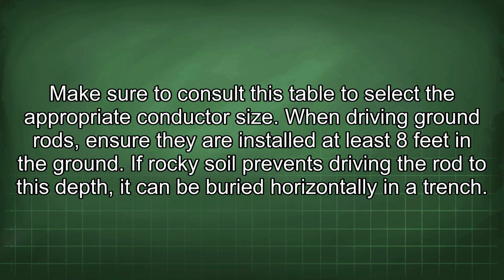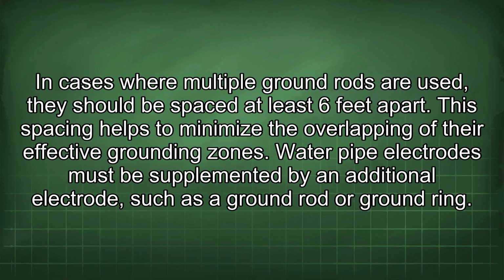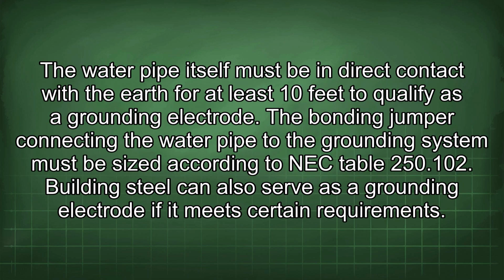When driving ground rods, ensure they are installed at least 8 feet in the ground. If rocky soil prevents driving the rod to this depth, it can be buried horizontally in a trench. In cases where multiple ground rods are used, they should be spaced at least 6 feet apart. This spacing helps to minimize the overlapping of their effective grounding zones. Water pipe electrodes must be supplemented by an additional electrode, such as a ground rod or ground ring.